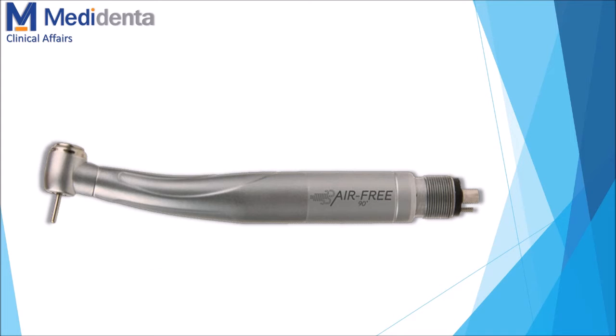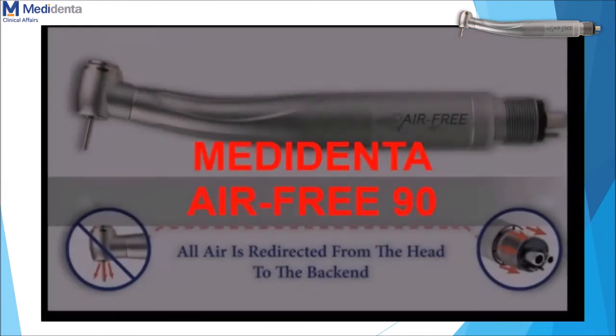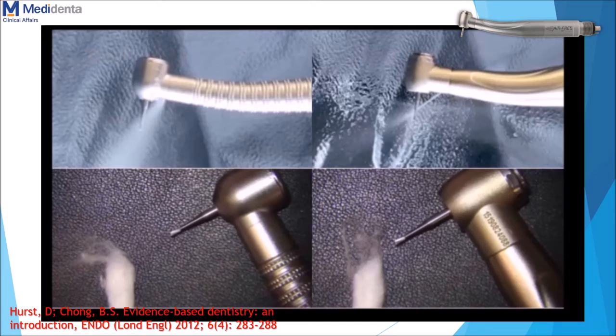Let's talk a bit about the emergency procedure itself and what we should do to minimize the risk of contamination. As I mentioned before, we have to face all emergencies as if we are treating an infected patient, so we should minimize the use of high speed. But in an emergency situation there's no way of removing the caries lesion and having access to the pulp chamber without using a high-speed bur. One possible way of reducing the aerosol is using the air-free type of handpiece. In this video you see the comparison between a regular handpiece and the Air-Free 90. The difference is that in traditional high-speed handpieces, the air is blown at the head of the handpiece, and with water creates water spray that increases aerosol formation. With the Air-Free 90, the air goes to the back end of the handpiece, escaping through holes there, so you still have water but you don't have the air as another component to increase the spray formation.